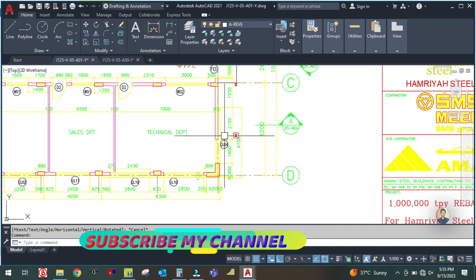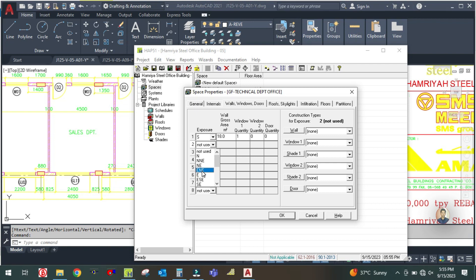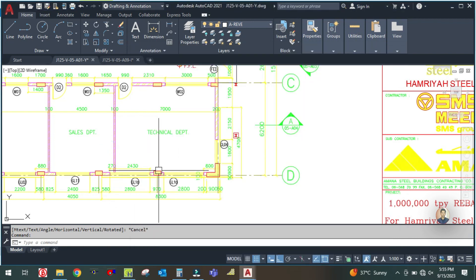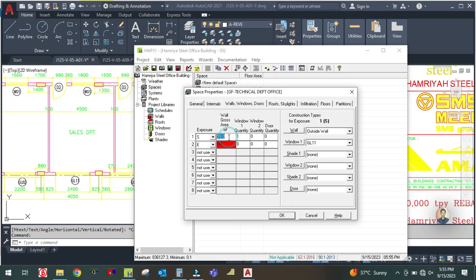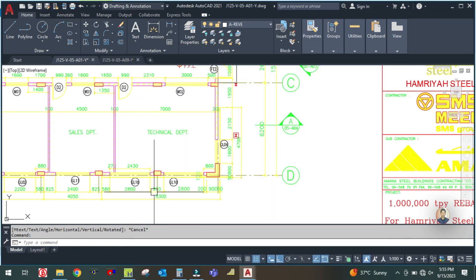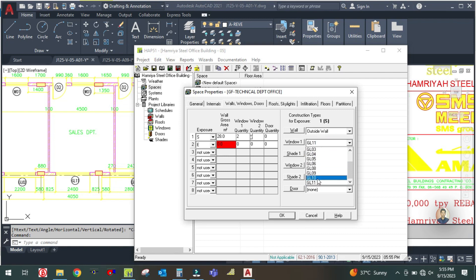Select south exposure and east exposure. The south exposure is 7 by 4 meters, which equals 28 square meters. Enter 28 here. There are two windows on the south exposure, both GL10. Select two windows and GL10 for both.